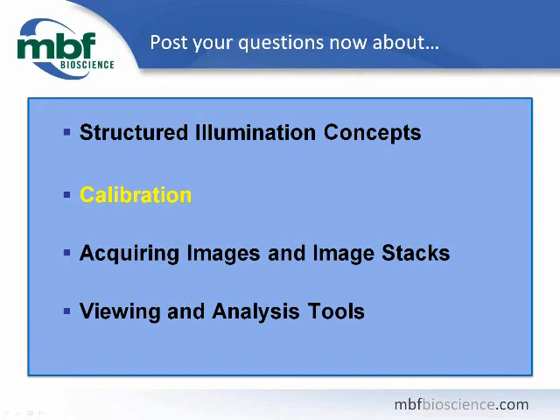We're asked if procedures will differ using the workstation version of Stereo Investigator or Neurolucida. You can only use this device when it's connected to the microscope. A workstation license will not be appropriate for imaging because it does not control hardware — you have to use the full version. The procedures for imaging and calibrating the ApoTome are exactly the same in Neurolucida and Stereo Investigator. We're working with Stereo Investigator for this webinar.